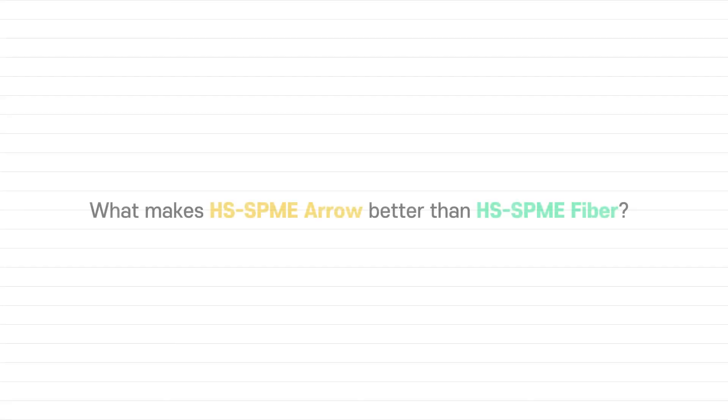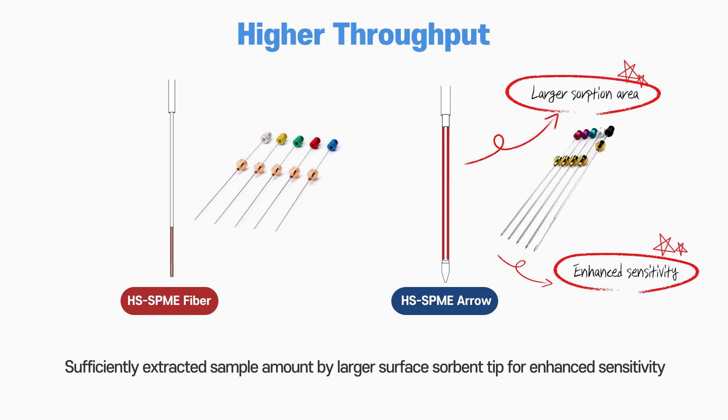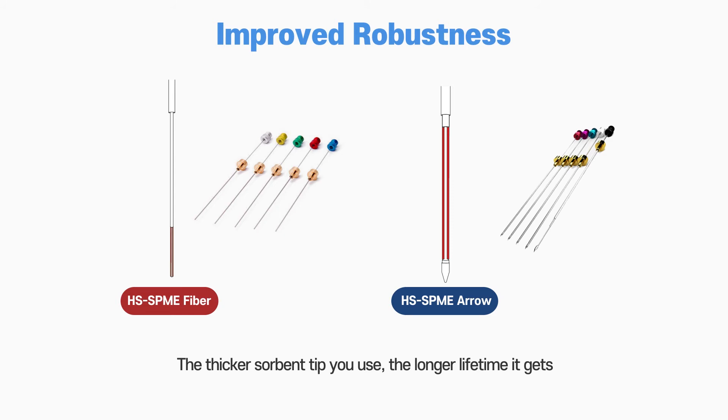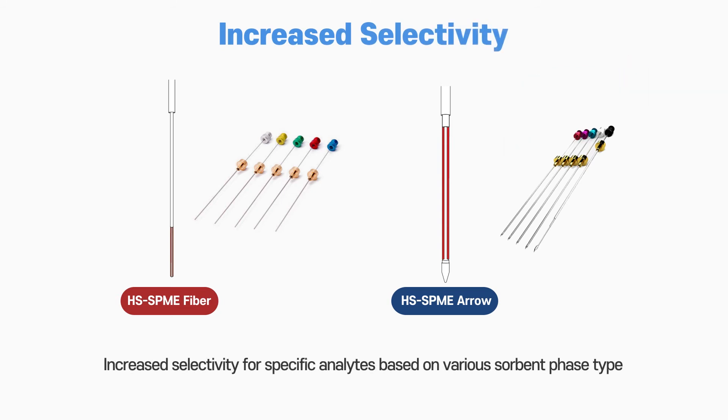What makes Headspace SPME Arrow better than Headspace SPME fiber? Higher throughput. Sufficiently extracted sample amount by a larger surface sorbent tip for enhanced sensitivity. Improved robustness — the thicker the sorbent tip, the longer its lifetime. Increased selectivity for specific analytes based on various sorbent phase types.